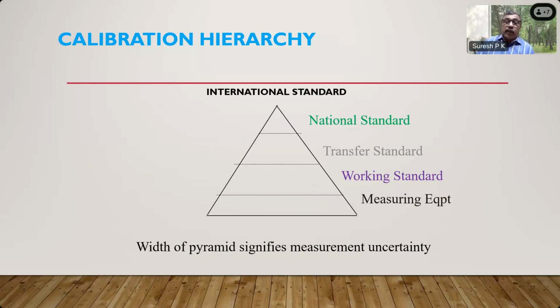So as you can see, the pyramid goes from the international standard at the pinnacle, to the national standard, to the transfer standard, to the working standard, to the measuring equipment. As you go away from the national standard, the width of the pyramid signifies the measurement uncertainty. I think you are familiar with the term uncertainty. Uncertainty is the lack of certainty. When you make a measurement, you would say it is 5 mm. You are certain that it is 5 mm within a limit of, say, 5 mm plus or minus 0.001 mm. That is the uncertainty associated with that measurement. That bandwidth, the uncertainty bandwidth, will get slightly bigger as you go to the bottom of the pyramid.